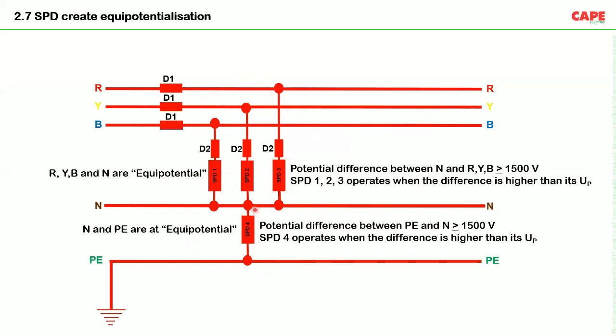Earth is connected to neutral, neutral is connected to the other three phases. So basically everything is interconnected. As a result, there is no potential difference. Even if there is a potential difference, it is lesser than the voltage impulse withstanding capacity of the connected load. So this is how an SPD works. And you must understand that this kind of equipotential bonding is happening in a few nanoseconds or a few microseconds. It's very, very fast. So there is no device which can detect the transient and switch off your appliance. The only opportunity or the only chance is to have this kind of device.